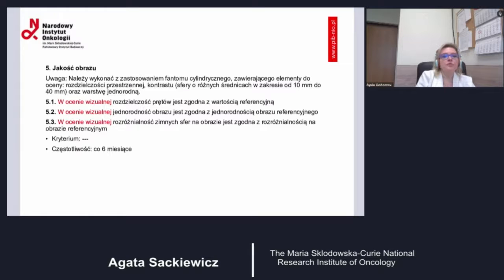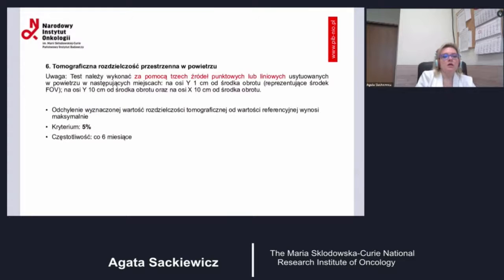The fifth test is the image quality. This test should be performed using a cylindrical phantom containing specific elements to assess spatial resolution. We should also check whether it is in line with the homogeneity of the reference image. We also have to check whether there is appropriate differentiation of the cold spheres in the image, in line with the differentiation in the reference picture, and this test can be performed every 6 months.